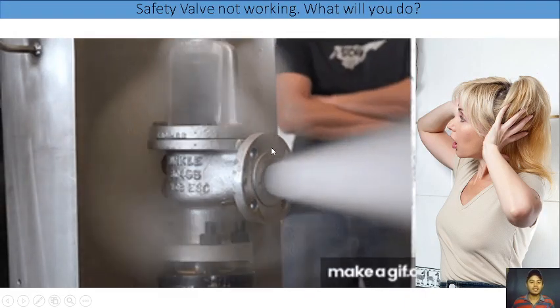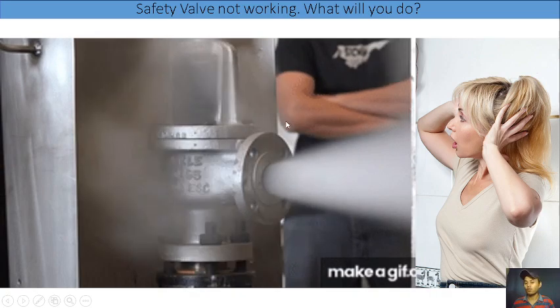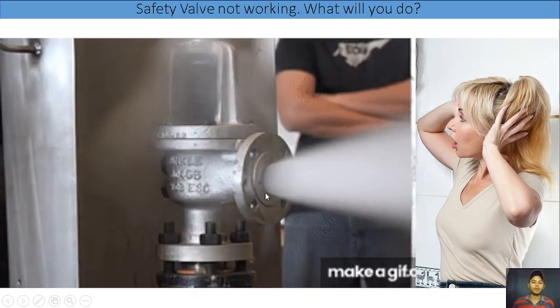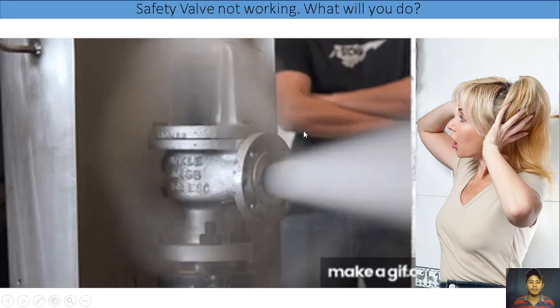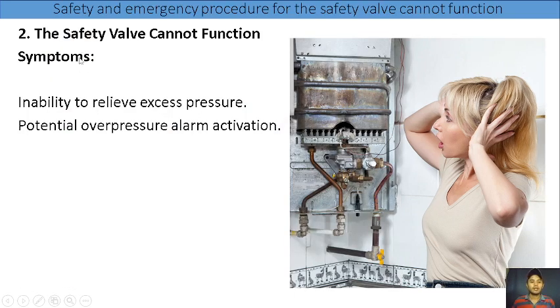Okay, next. Safety valve not working. What will you do if your safety valve is not working? So symptoms: inability to relieve excess pressure, and the potential overpressure alarm is activated. So the overpressure alarm activates, and hopefully the boiler will shut down from overpressure. But if it doesn't shut down, then there will be a problem, especially if the safety valve is not working.